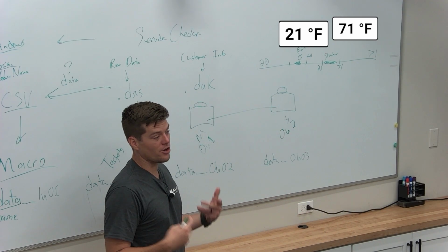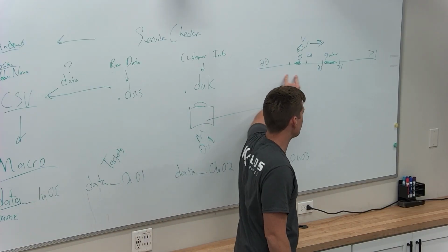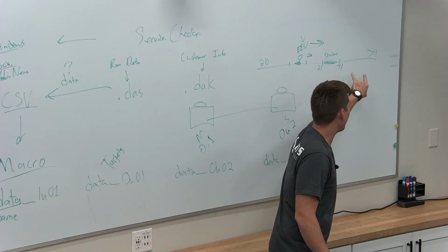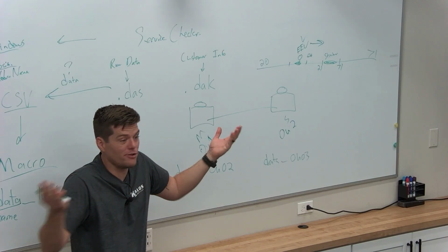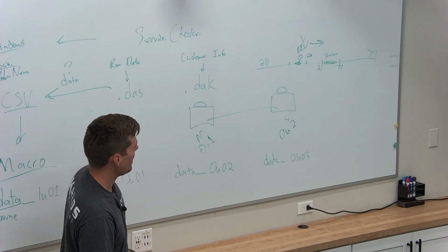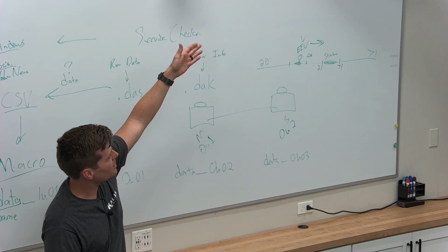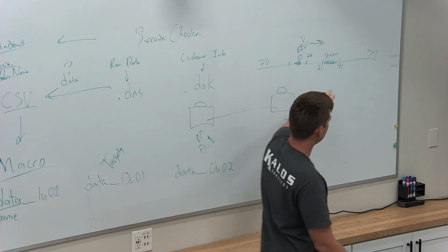And so the strainer is plugged, right? It's pulling low pressure on this side, and it's stacking on this side. That's how we troubleshoot refrigeration problems in any refrigeration system. That's not just VRF. That's just basic air conditioning. And so for this, it lays it out in a format to where we can actually see what's on this side, what's on that side.